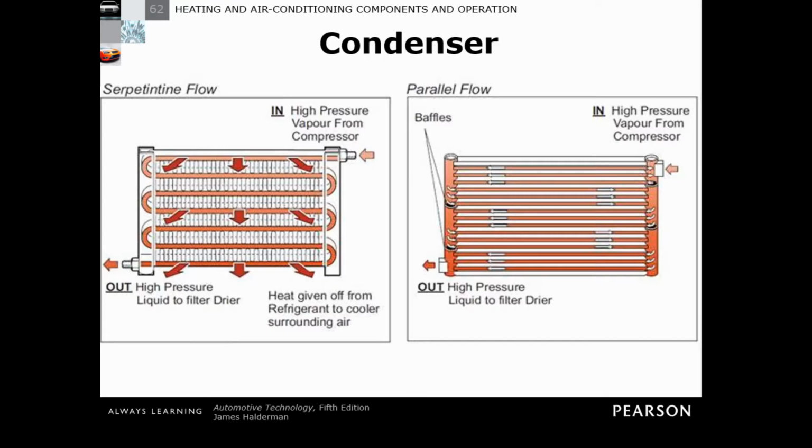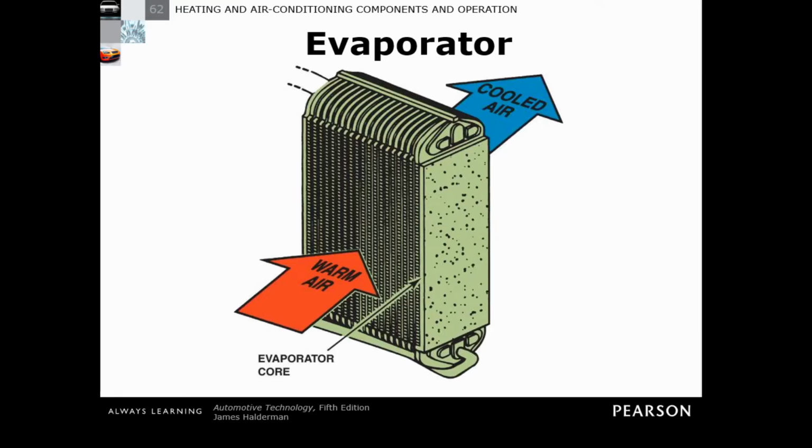So that is one half of our system, okay? The other one is the evaporator, which is going to operate exactly the same way. The difference is we are doing the latent heat of evaporation here, and what we're going to do is absorb heat into that so we can condition the cool air going through the evaporator. So when this goes through, what happens is the exact opposite. We will boil the freon. We will make a really low pressure, which will make the freon boil into a gas, and as it boils, we can pull a lot of heat out of the air, okay?